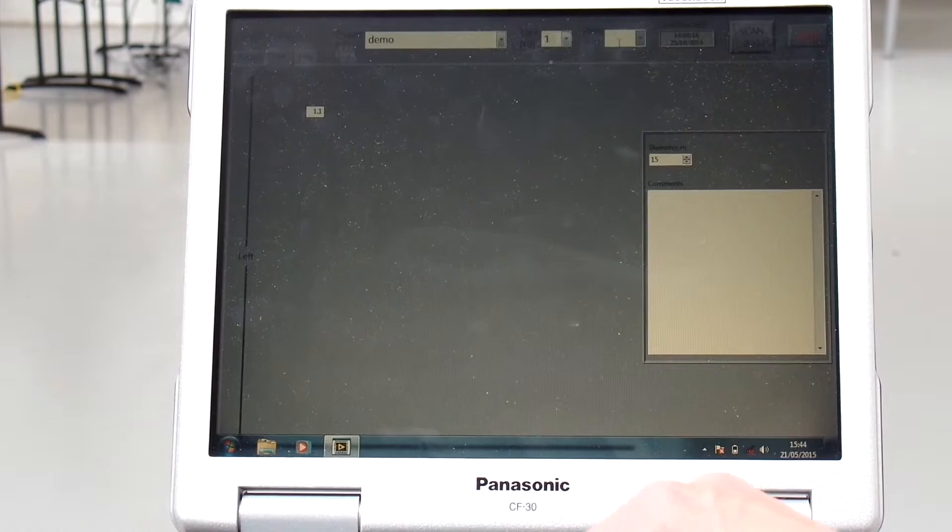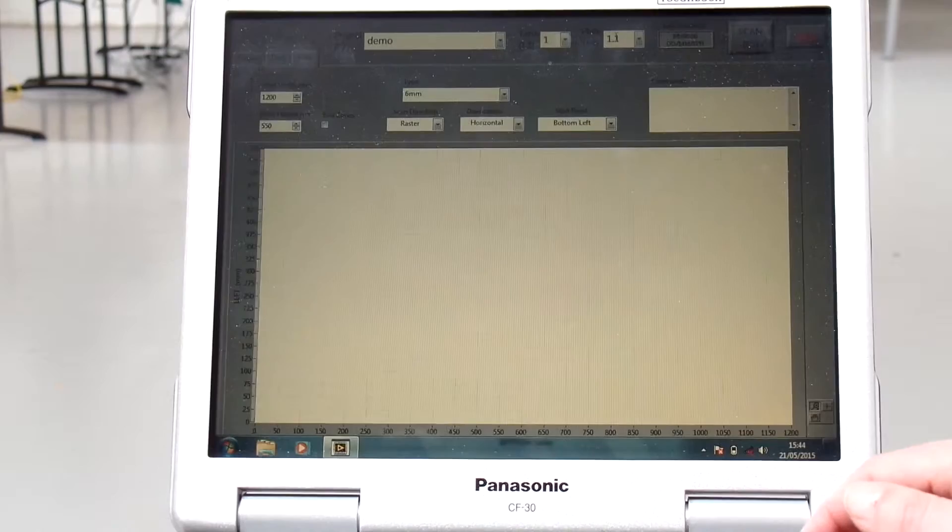Once in the tank screen, it will appear empty as no scan data has been collected yet. We select the diameter of the tank that we are going to inspect, either by typing a value in or using the up and down buttons. When we are happy with the tank diameter, we then enter the plate number that we are going to scan first, using the row convention. So Row 1, Plate 1 will be the first plate we inspect, and then we press return. We then return to the plate screen as shown.